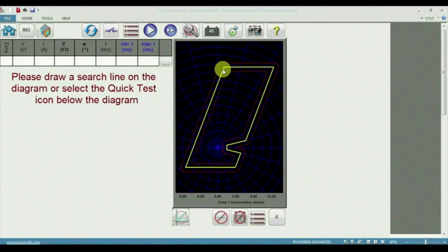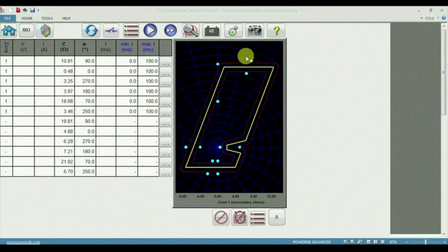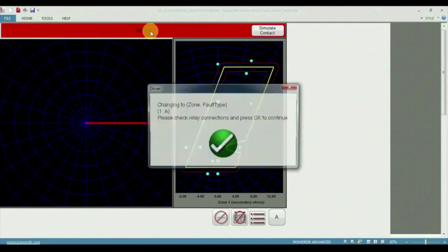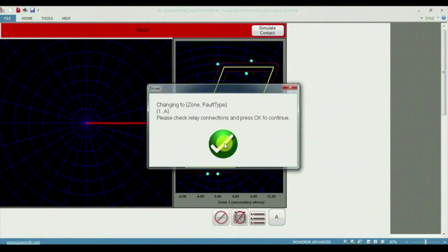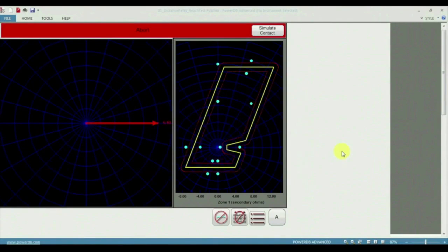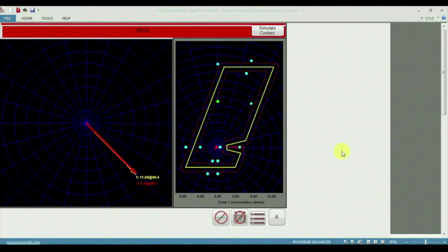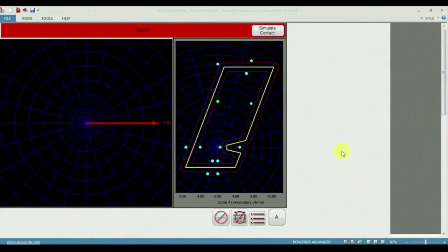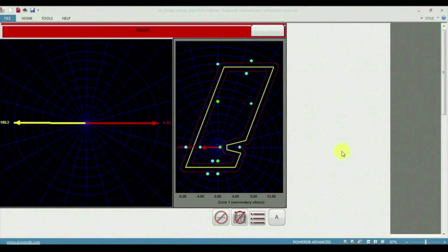So when I click on the Quick Test, I get the characteristics along with load encroachment in line with the relay characteristics. Click on this, it will randomly select the points. If you wish to click more points, you can also do that. Then click on this play button, put a tick mark. Now you can see at each and every point that we have selected, it is injecting the respective current, voltage and impedance, and this is going to trip the relay and we will be getting the feedback.